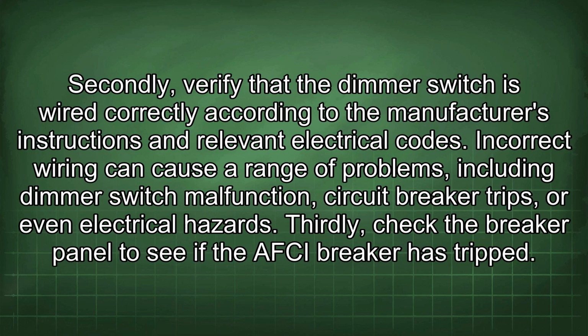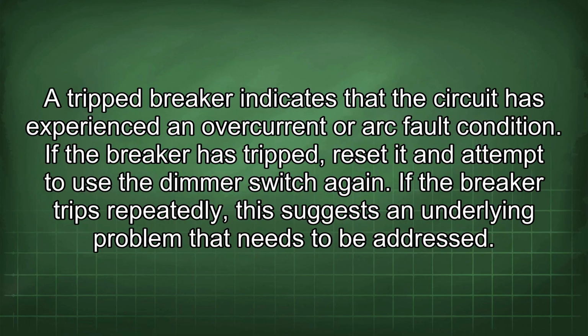Secondly, verify that the dimmer switch is wired correctly according to the manufacturer's instructions and relevant electrical codes. Incorrect wiring can cause a range of problems, including dimmer switch malfunction, circuit breaker trips, or even electrical hazards. Thirdly, check the breaker panel to see if the AFCI breaker has tripped. A tripped breaker indicates that the circuit has experienced an overcurrent or arc fault condition. If the breaker has tripped, reset it and attempt to use the dimmer switch again. If the breaker trips repeatedly, this suggests an underlying problem that needs to be addressed.